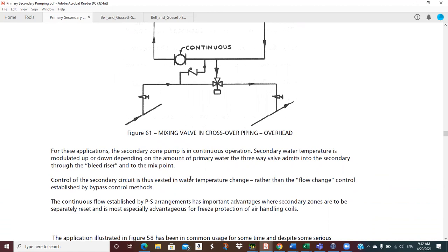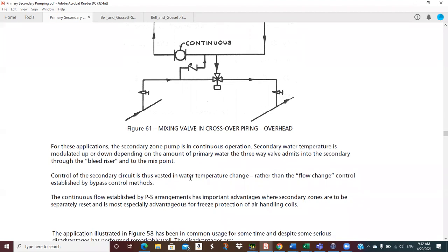Now remember from our control valve sizing presentations, we could control with flow or we control with temperature. And that temperature control curve was that nice 45-degree line, which was ideal. And so temperature control at constant flow gives you better control than flow control, because remember, especially on a 20 delta T coil, you had that kind of banana looking curve up at the top where you had to reduce flow to, like, I don't know, 10% to get a 50% reduction in heat transfer. And so that would be an advantage of this type of arrangement, that you get temperature control instead of flow control. And so your control system would probably be better and occupants would probably like it more.